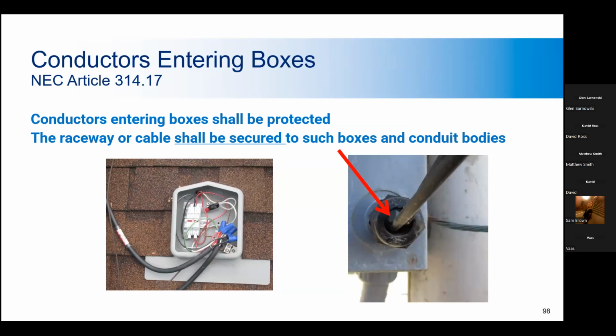Here's another common error where fittings used for conductors to enter an enclosure are missing or not installed. You can see over here the fitting is not tight to the wire, so it doesn't provide the stability that is the point of that kind of connector, and so that would fail for that reason. On the left, some of these wire nuts are not rated for outdoor conditions, even though this is kind of inside the enclosure. The humidity and the temperature is the same as outdoors, so it's essentially an outdoor space. Also, you're supposed to run the wires through the knockouts in these systems, and they ran the conductors right up underneath the lid, which is obviously not okay. So this would fail for that reason.